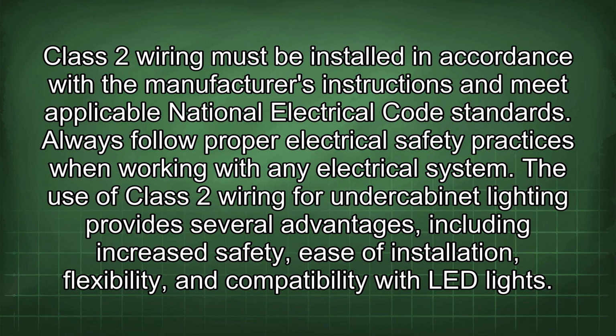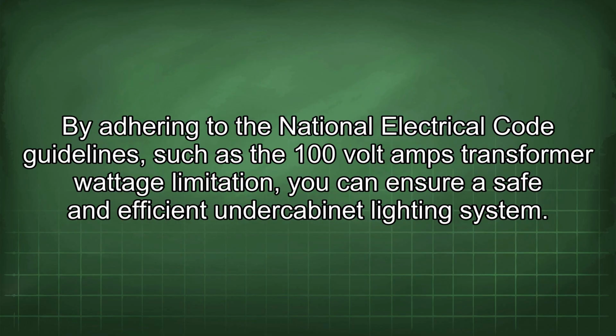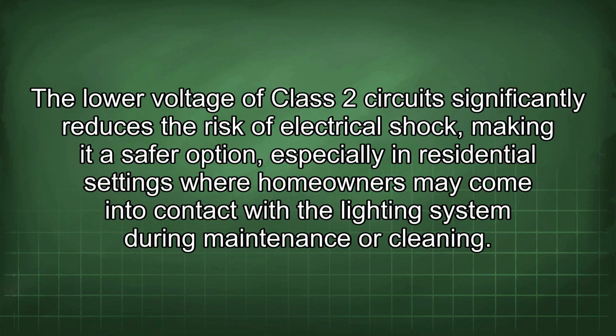The use of Class 2 wiring for under-cabinet lighting provides several advantages, including increased safety, ease of installation, flexibility, and compatibility with LED lights. By adhering to the National Electrical Code guidelines, such as the 100 volt amps transformer wattage limitation, you can ensure a safe and efficient under-cabinet lighting system. The lower voltage of Class 2 circuits significantly reduces the risk of electrical shock, making it a safer option, especially in residential settings where homeowners may come into contact with the lighting system during maintenance or cleaning.